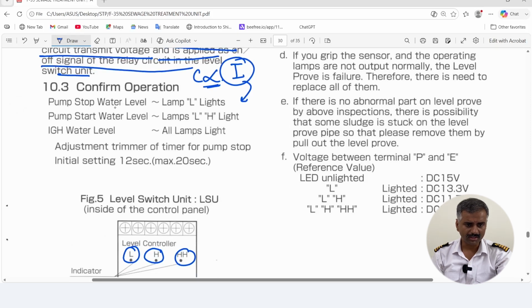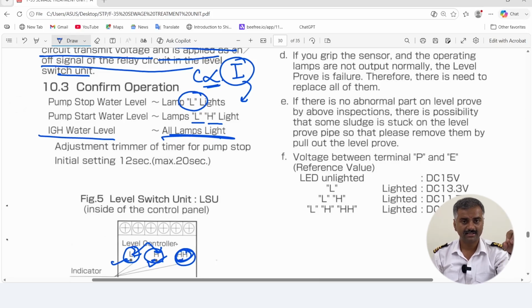You will see the operation will be like this. The pump stop will be at low level, at this level. The pump start level will be the LH light. Both the lights will glow when you have to start the pump, because the low level sensor is active and the high level sensor is also active. And while you are trying out, very important, don't get confused about why your low level light is glowing. While you are trying out, all three lights will be glowing. See, at high water level all lamp lights will glow, not only this one, because all three sensors have water, right? These three sensors are already dipped in water, so you will have all three lights. So don't get confused when you are trying out the alarm. All three lights will glow all together.